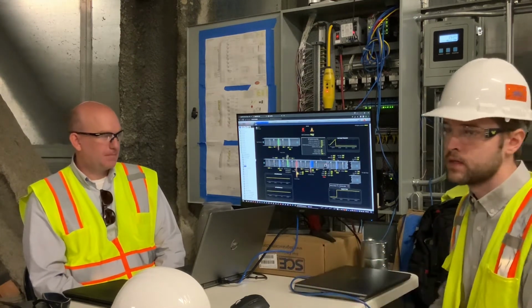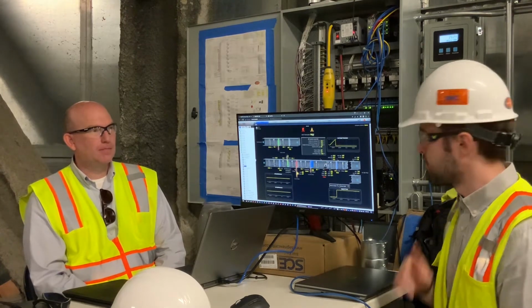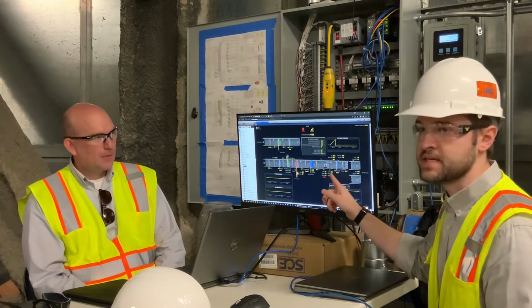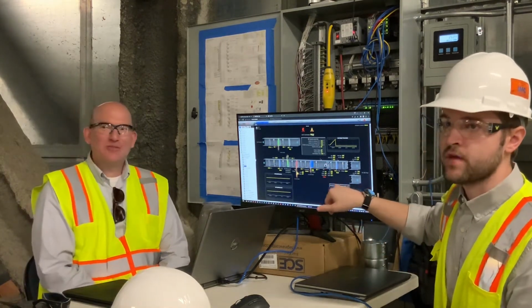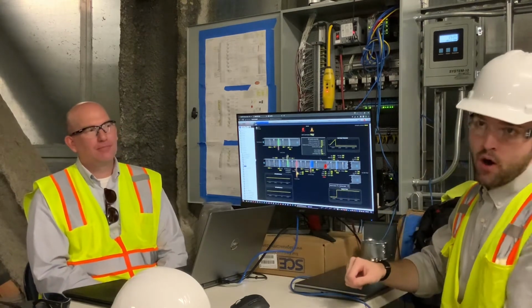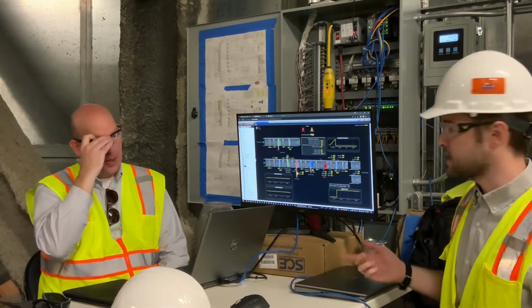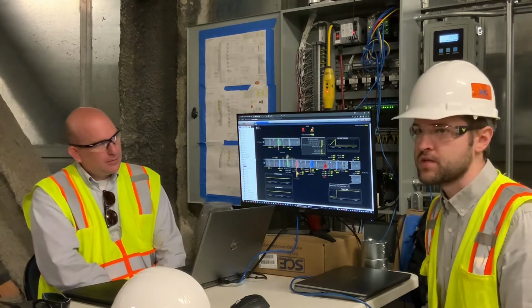Can one handle the load? I don't believe it's sized for the full load, although right now it looks like it's doing all right. As I said, one of them is 25% speed, though it's not actually at 25. We're telling it 25. Both of them are in hand. One of them is in hand, off. The other one is in hand, I think at like 50 hertz, but that's still not max. And we're seeing 3.1 inches at the discharge of the unit. So it does all right on one fan.